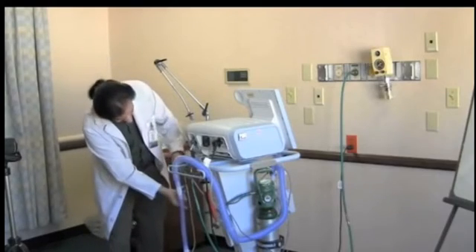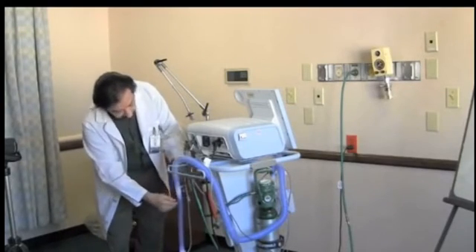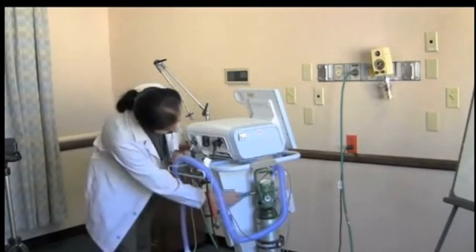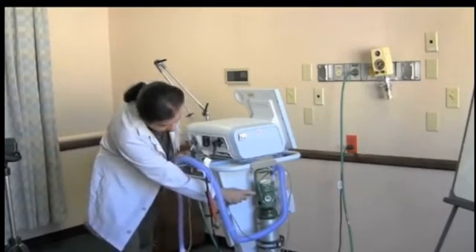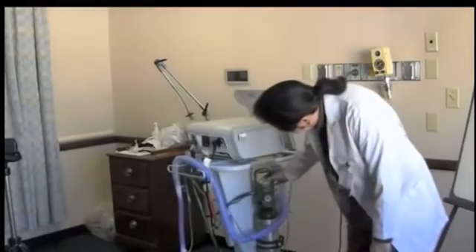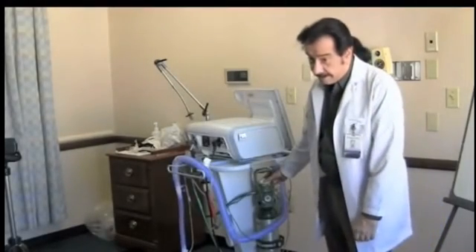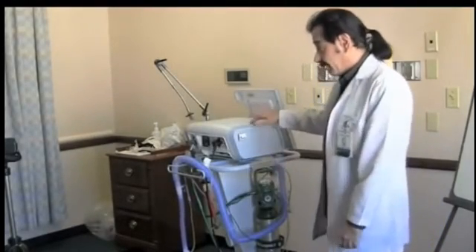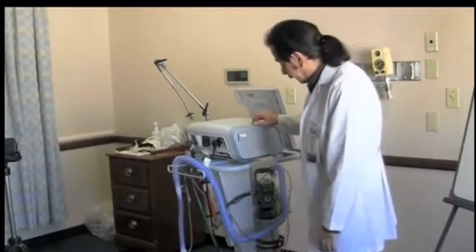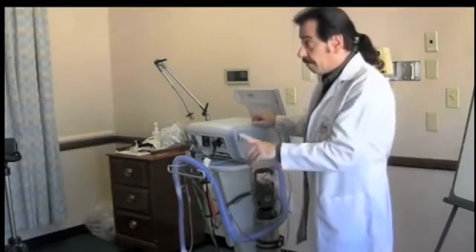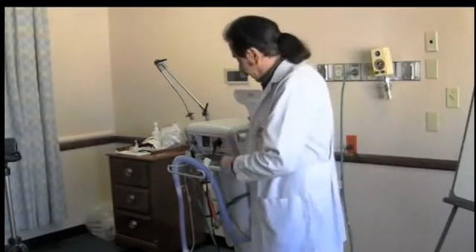Then you can hook up 2 E-cylinders. The hose goes into the auxiliary port on the E-cylinder, and then you turn the E-cylinder to the auxiliary setting to supply 50 psi to the V60. Only run one at a time. You can hook 2 tanks up, but only run one at a time. Okay.